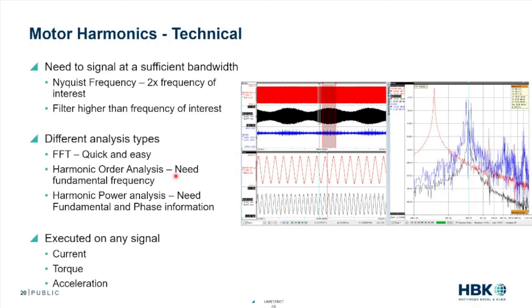And then we can do things like harmonic power analysis. Where if we know the different harmonic orders and we can identify the harmonic phasing, we can start to understand what is the power from these different harmonics. How much energy am I losing because of these different harmonics? And this is where we get really into a deep understanding. If I'm doing a third order or a third harmonic injection, is that creating extra losses that mitigate its purpose?